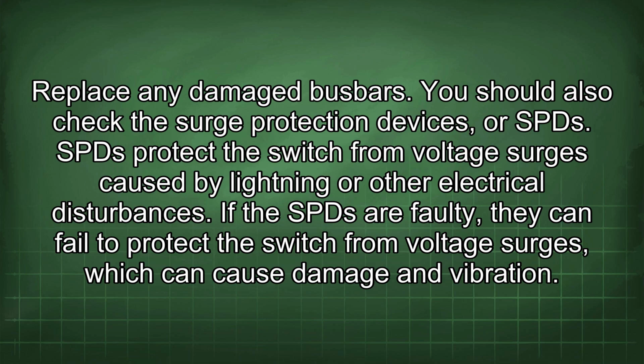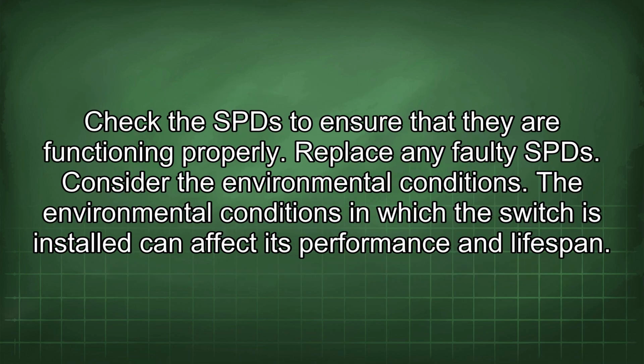You should also check the surge protection devices, or SPDs. SPDs protect the switch from voltage surges caused by lightning or other electrical disturbances. If the SPDs are faulty, they can fail to protect the switch from voltage surges, which can cause damage and vibration. Check the SPDs to ensure that they are functioning properly. Replace any faulty SPDs.